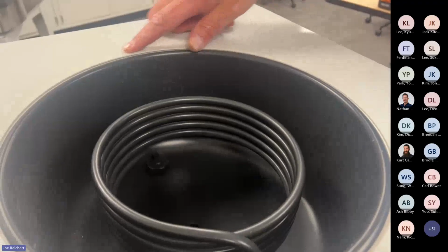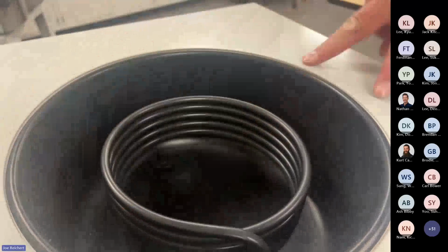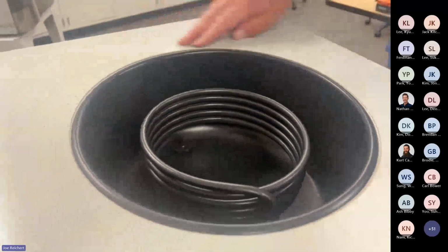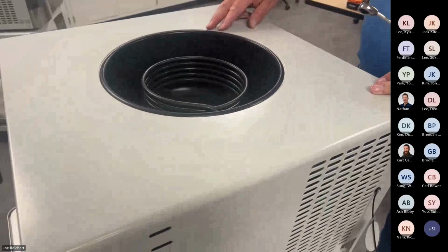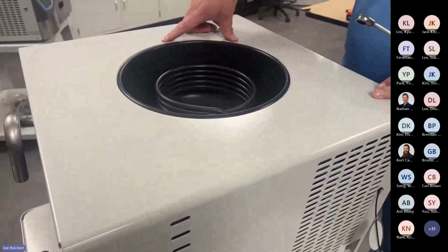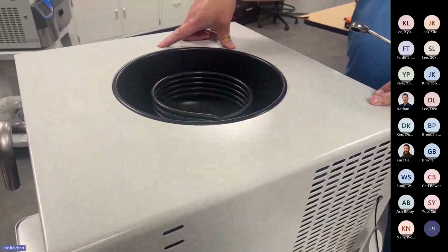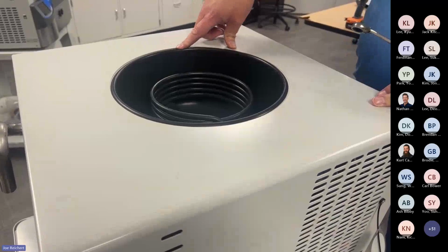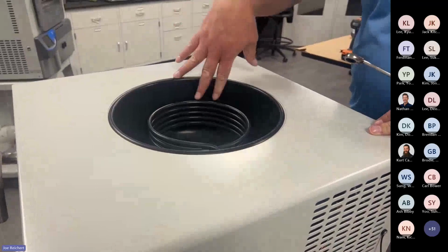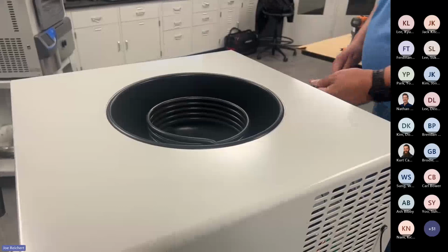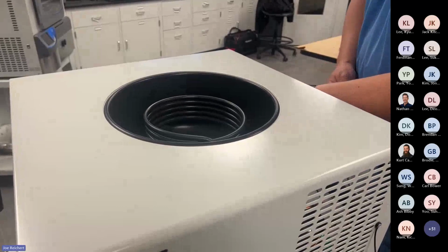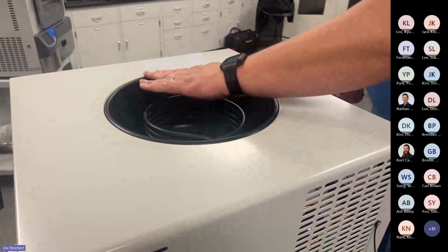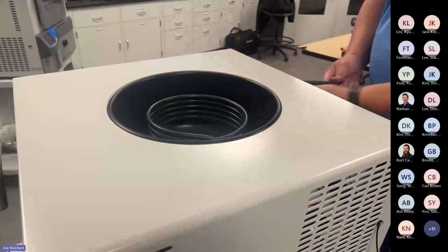And on our old systems, we only had 4. We had 2 in the front and 2 in the back. Now we do 6, so it's supported more. But if you had a threaded stud break off or pop off the weld, then the chamber might sink down inside, and that will not seal for a chamber. So you always want to make sure that that rim is up above the side of the chamber.